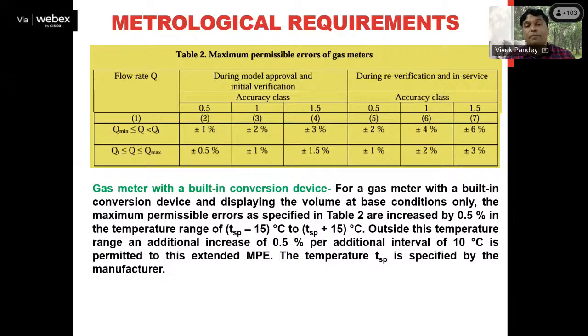T specified minus 15 degrees Celsius to T specified plus 15 degrees Celsius, okay. If the temperature is changing, suppose your gas is being transferred to the gas meter and the temperature is not 30 degrees Celsius, it is more than or less than 30 degrees Celsius, then obviously it will affect the measurement result. Suppose the temperature is 25 degrees Celsius, it will change the volume or the quantity. So accordingly, the correction should be made, fine, by the correction device.